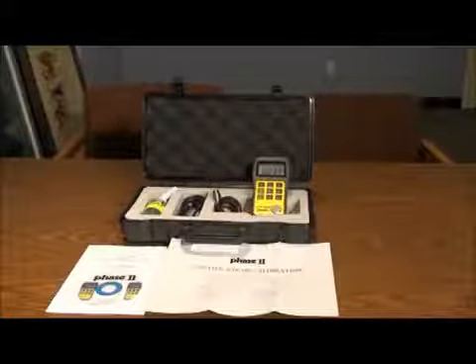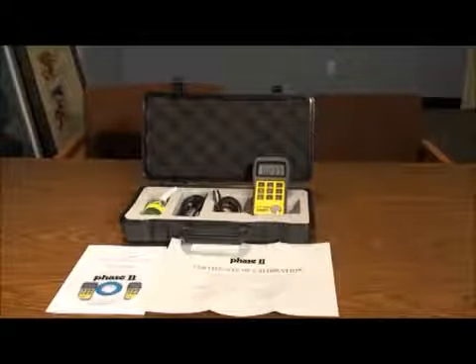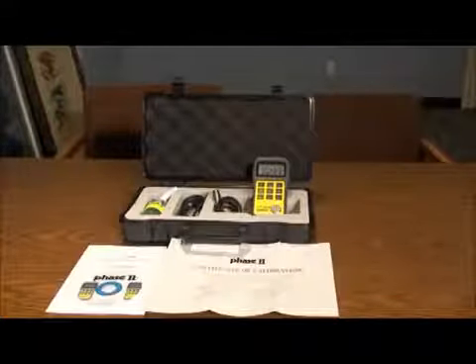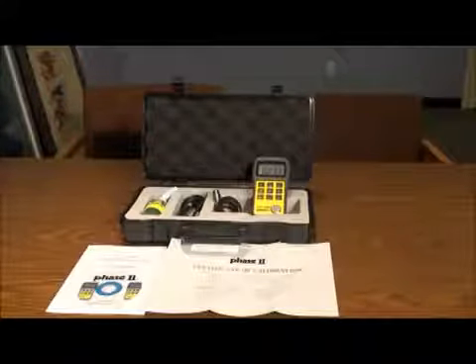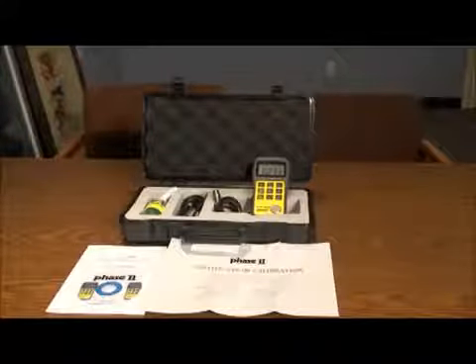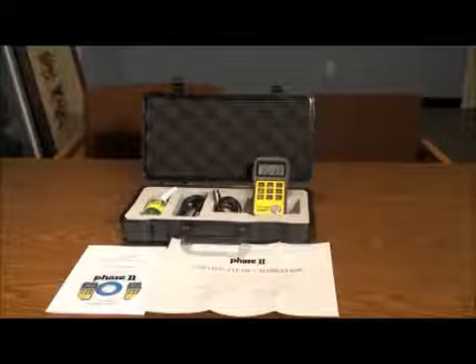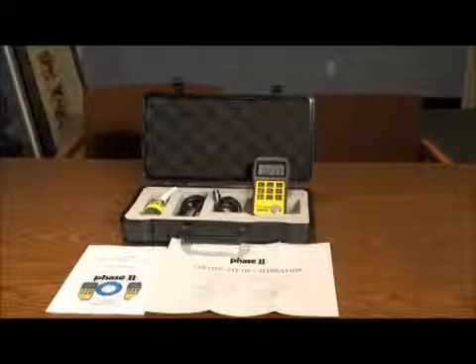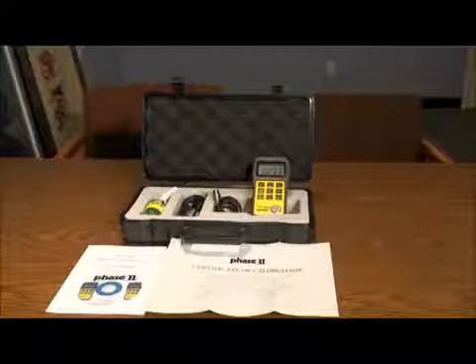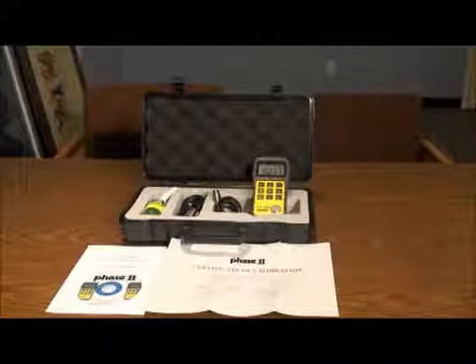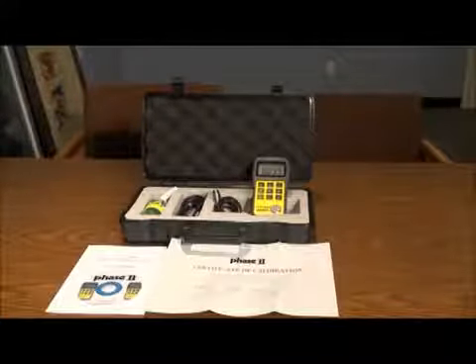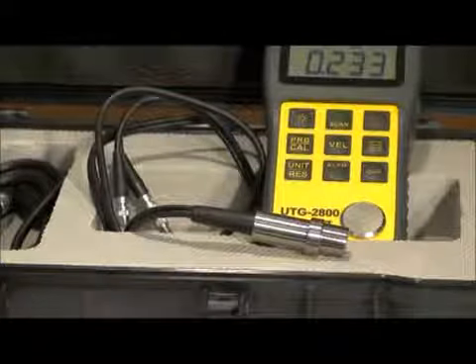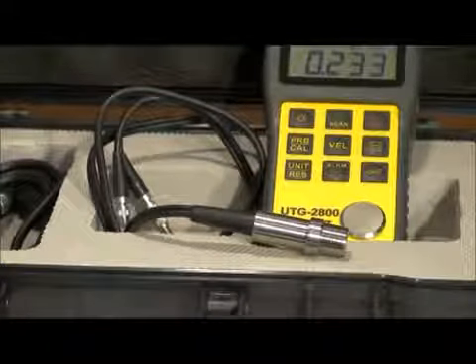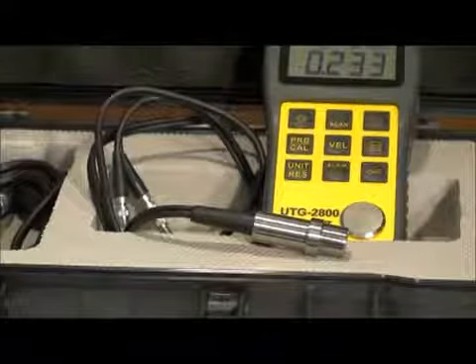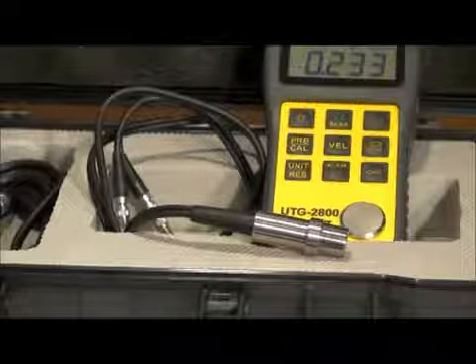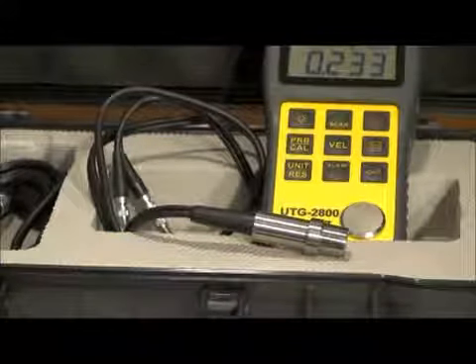This is an instructional video detailing the applications and functions of the Phase 2 UTG 2800 ultrasonic thickness gauge. The UTG 2800 is designed to test metallic and non-metallic materials as long as they have parallel top and bottom surfaces and sound waves can travel through the material. The technology incorporated utilizes a simple ultrasonic dual-element transducer that transmits and receives sound waves.